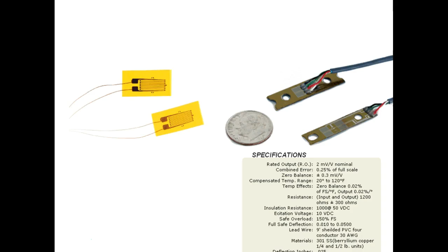So it sounded like one of your load cells went out on you. You cut it out—yeah, we cut it out—and then recalibrate it. But the bridge wasn't weighed perfectly every time; it depends on where you put the weight, it would probably give you a different reading. So y'all pretty much measure it at the same time. Well, it was a tank, so it was actually centered.